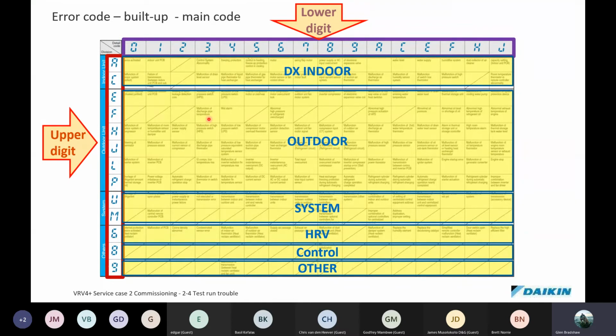Very often when technicians see a fault, they tend to think that the component is faulty. No. Okay, what is very often happening is it's telling you that that component has sensed an abnormality in the system's operation. So the first thing you need to do, yes, confirm that the component is working properly. Okay, if it is, then the information it gave you is related to the operation of the system. Okay, so don't just keep trying to replace parts. Remember that each of these error codes is pointing you in a direction to try and fault find the system. All right, so yes, it could be a faulty component. Very often when it isn't a faulty component, then you need to start doing the legwork as to identifying what in the system was abnormal in its operation.